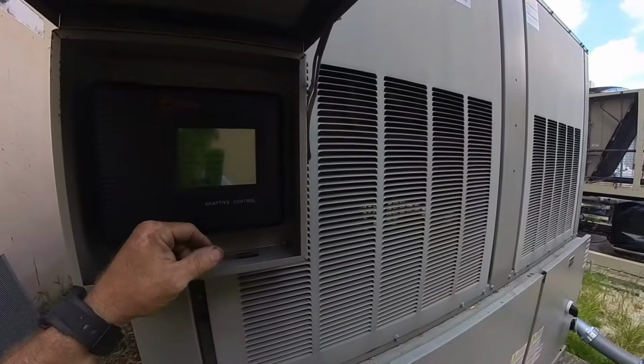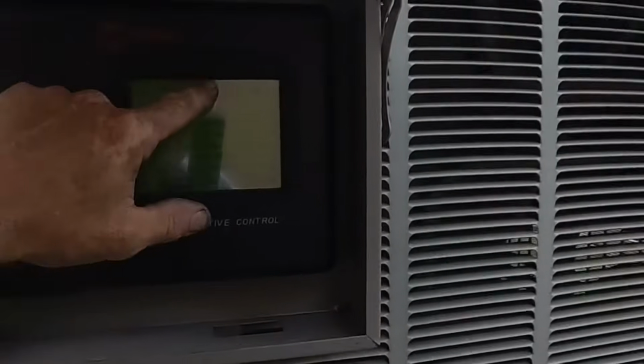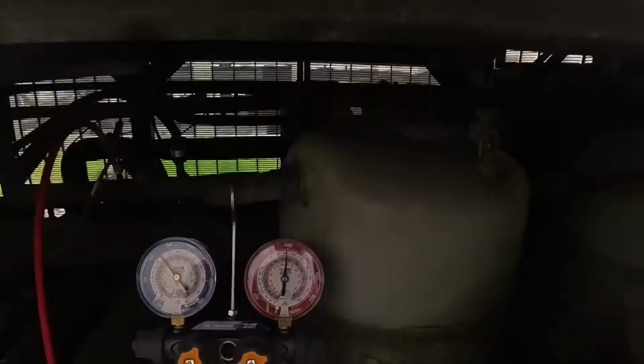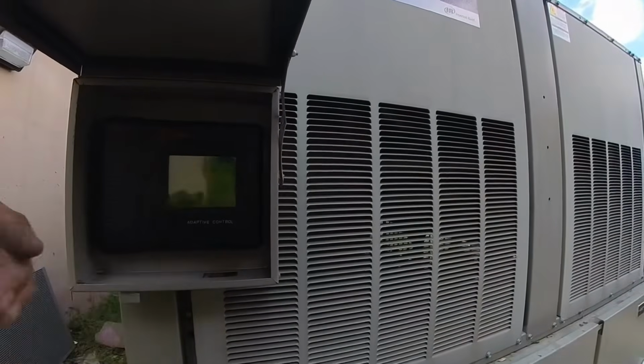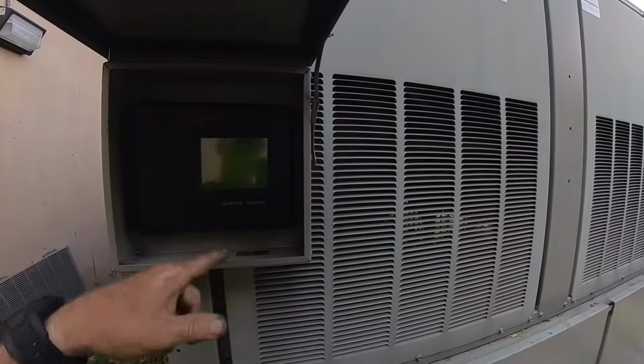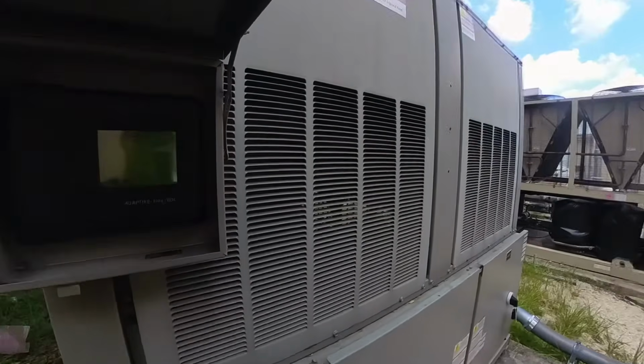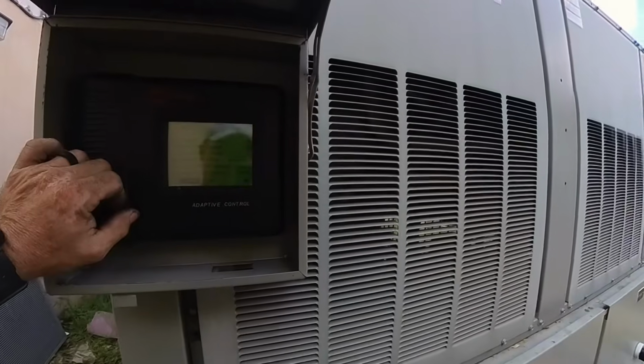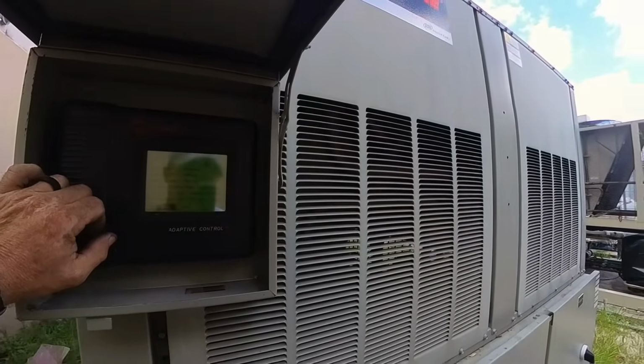Alright, I got the chiller started back up here. Both circuits are running. 56 entering, 48 leaving. Still a little high. Circuit 2 discharge pressure is 412. We are just a hair under 400, 398. So probably going to end up swapping out that transducer for that. Circuit 1 discharge is 403 over there. I'm sure these coils probably need to be cleaned since they've been doing a lot of construction around here. But it's also hot in school. Monitor this for a little bit and revisit this when temperatures come back down.